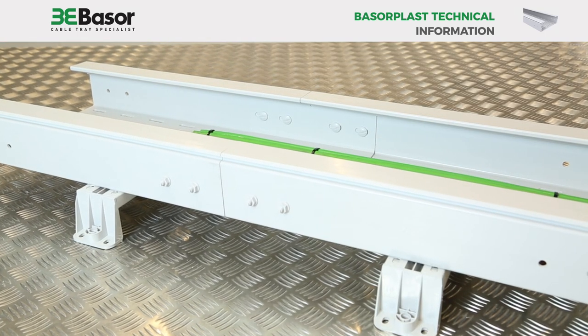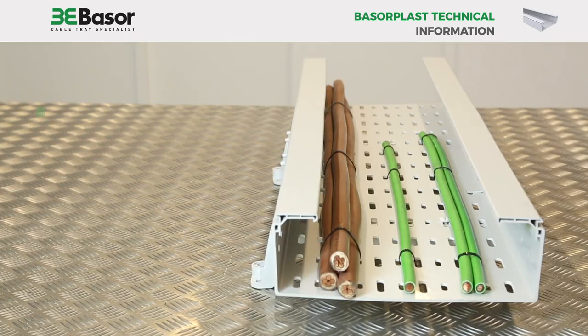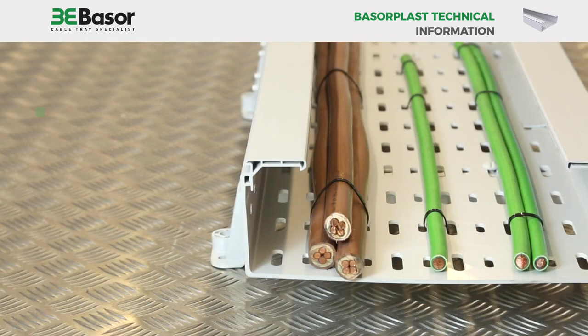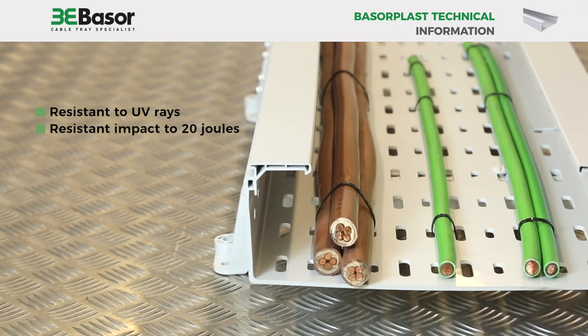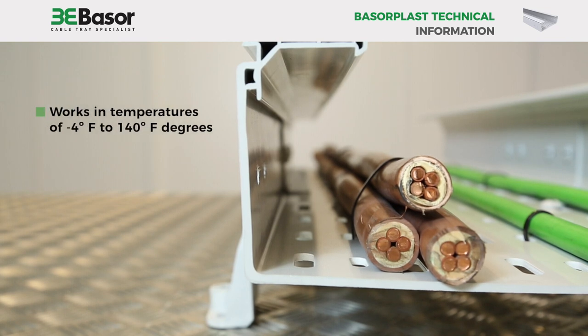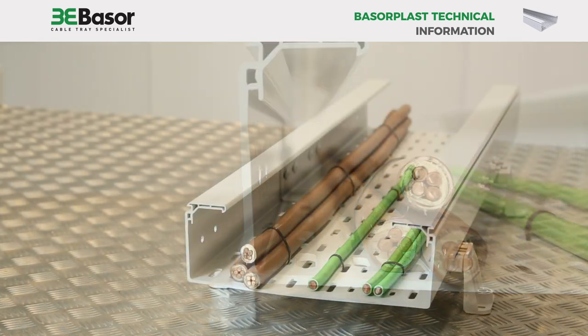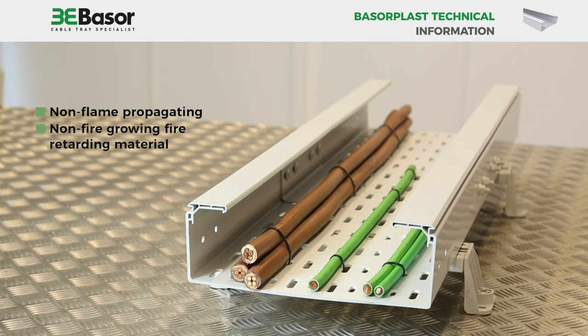Some notable characteristics of the Basorplast PVC cable tray system: it is a non-metallic, non-conductive cable management system. It is resistant to UV rays. It passes an impact strength test of 20 joules for the majority of the line. It works well in temperatures of minus 4°F to a maximum of 140°F. The Basorplast PVC is a non-flame propagating, non-fire growing, fire retarding material.